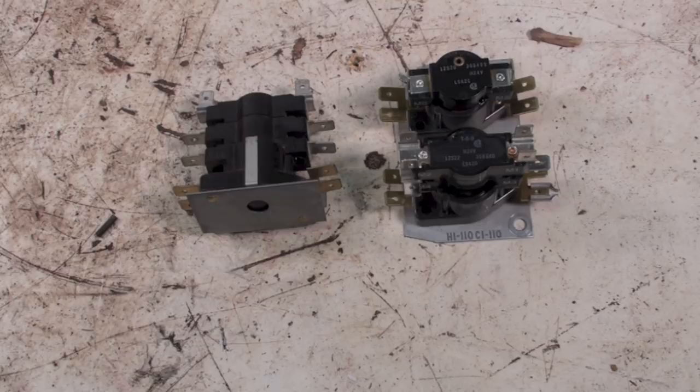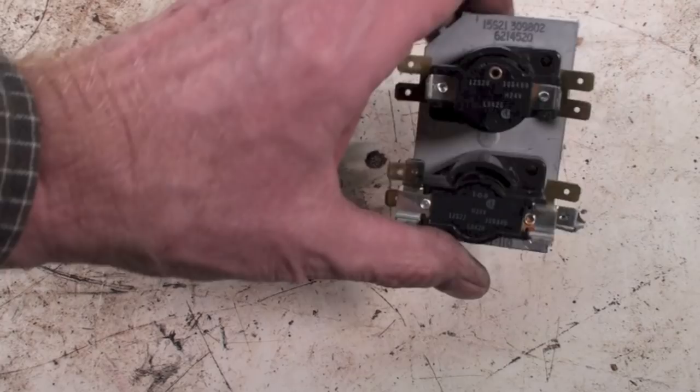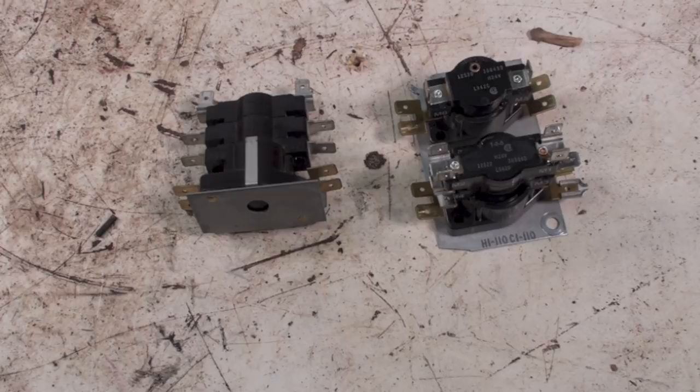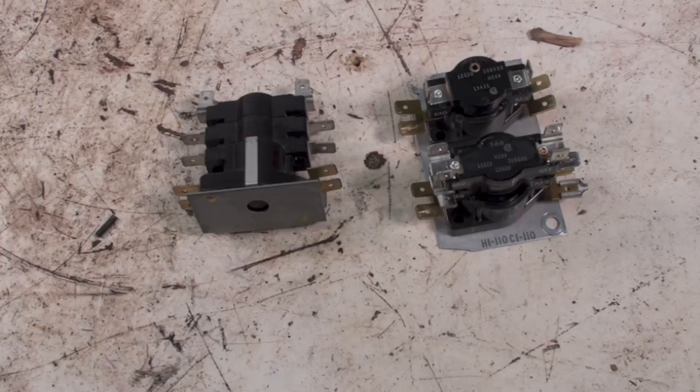So you need to make sure when you put these in, if you're not putting exact replacements or you're putting something that's not on the same plate. See, this is all on the same plate. And you got to make sure that they time off right. I mean, I would check them anyway to make sure that everything cycles right, but these sequencers, because they're a time-delay relay, you got to be aware of the timing on these things.